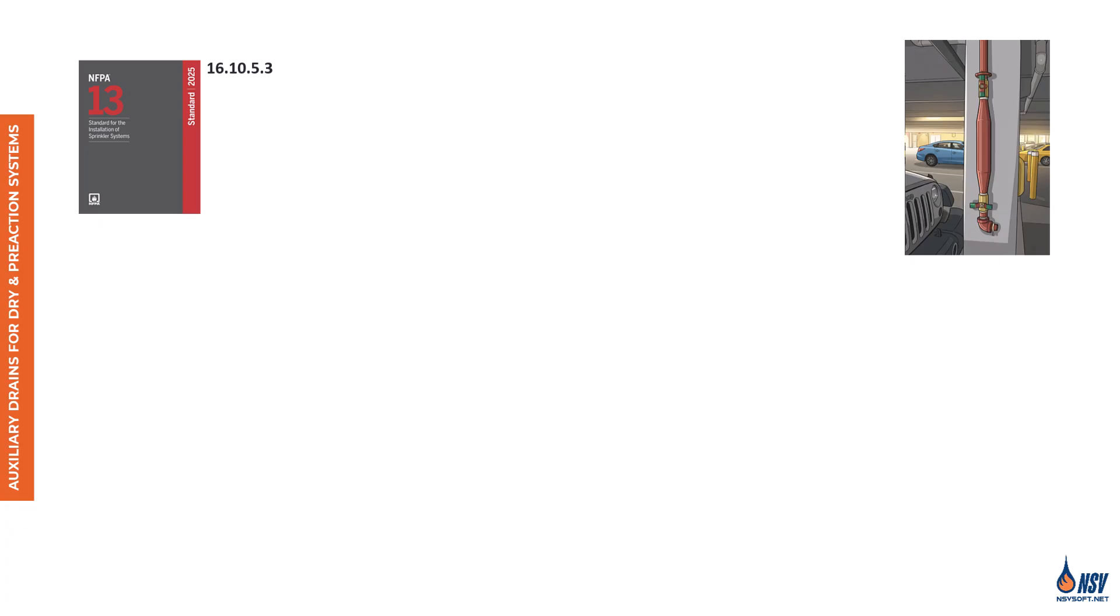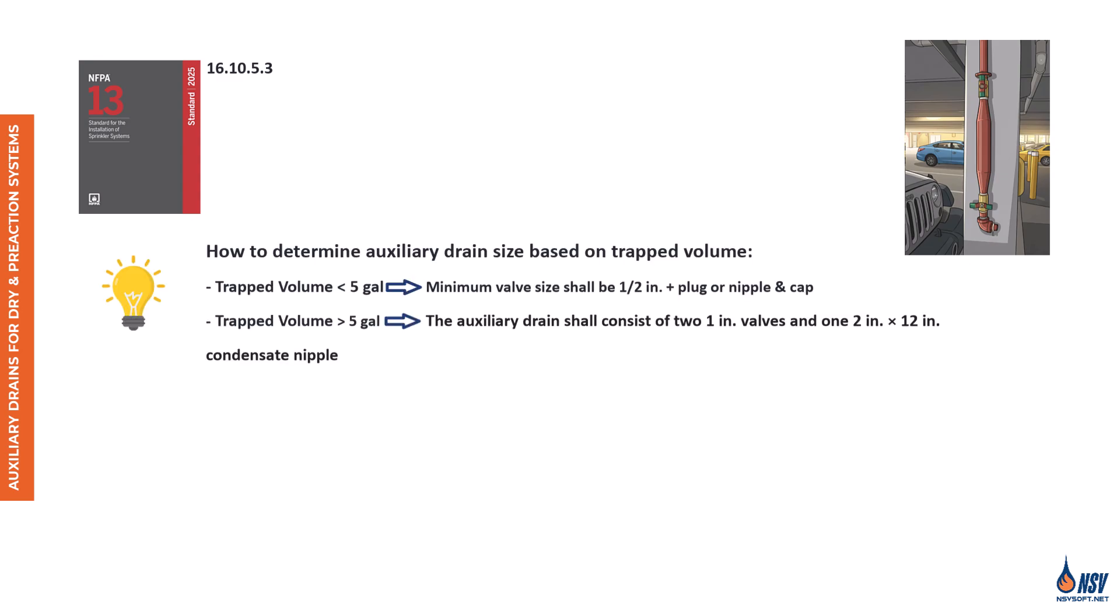It's important to ensure that all water is eliminated from dry and pre-action systems in areas subject to freezing. Any residual water can lead to excess corrosion when air is introduced into the system. In addition to confirming that the system can be properly drained, the designer must ensure that all piping is pitched correctly, as discussed earlier in the video. In these systems, condensation is a key concern. As temperatures fluctuate, moisture in the air condenses, settling at the low points of the piping. If this water remains and freezes, it can expand and potentially rupture the pipe.